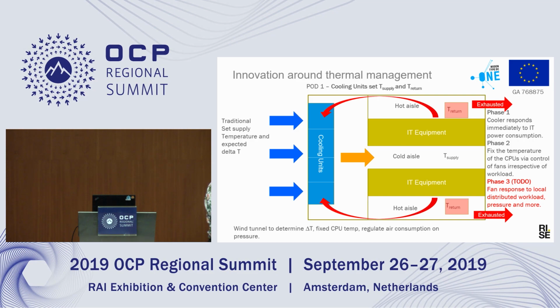What you want to do is try and match the supply flow rate to the flow rate through the IT equipment. So our first phase that we've achieved here in holistic control is linking together the aggregate information from the IT equipment to the cooling units. And that enabled us to trim back the cooling fans, which contribute to the other side of the PUE, and reduce that and allow us to run with a better PUE.